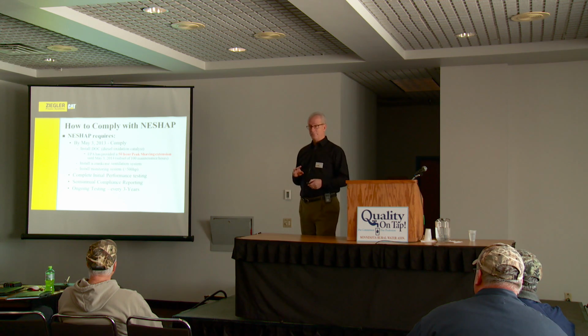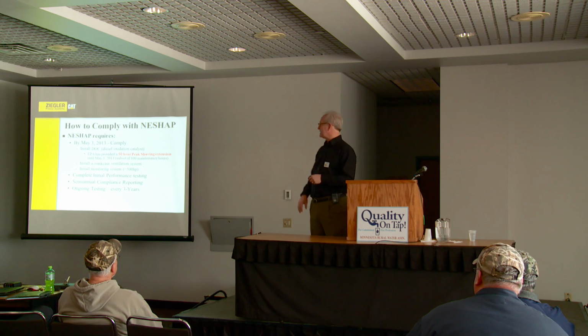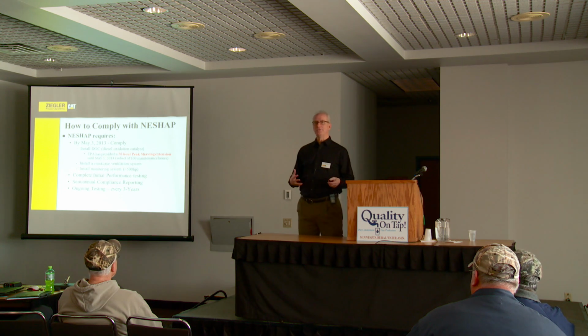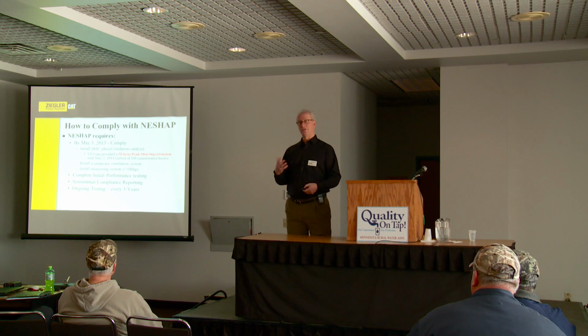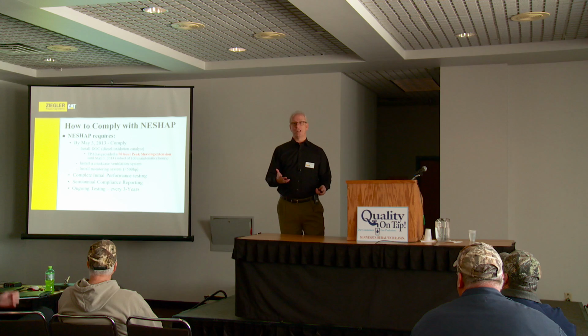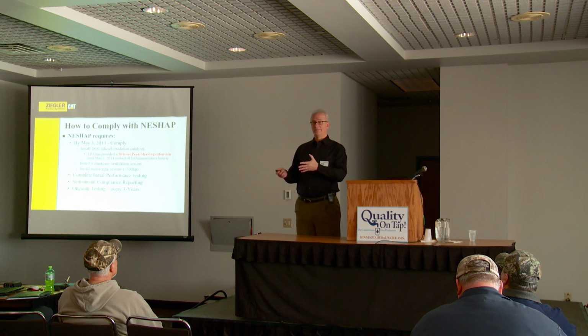Now, one of the things the EPA did in this rule, because they ruled on this last piece so late, is put in a provision that says users have 50 hours a year of peak shaving for 1 year. That lets people get a little bit of an extension. So, like I said, today, this is the way we go about getting it done. It wouldn't be done by May 3rd, it would probably be done by June or July. If you hadn't done 50 hours of peak shaving with your utility by then, you'd be fully fine, because the EPA says for a whole other year you can run up to 50 hours.